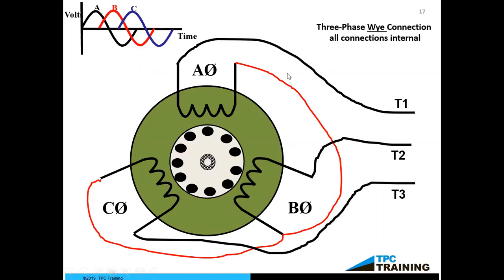So the two numbers that we don't want to see, and one of them on a digital meter would be OL, which signifies open line, and that would mean that one of these windings was open, and of course when a circuit is open, we have no current flowing, and if no current can flow, then we're not going to be able to turn that motor. So OL is not a great thing to see.